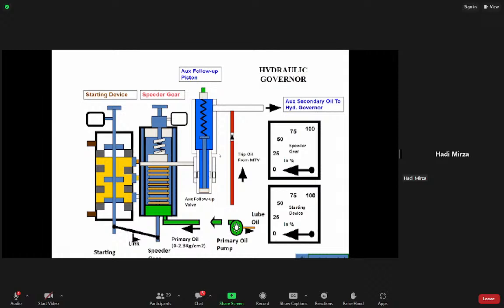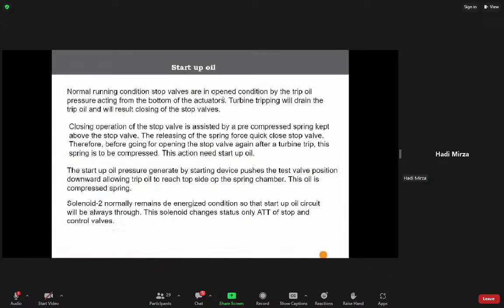Actually, this startup oil is required to reset the stop valves and hydraulic trip devices. In normal operation, stop valves are in opened condition and trip oil pressure acts from the bottom of the actuator. Turbine tripping will drain the trip oil and will result in closing of the stop valves. Closing operation of the stop valve is assisted by a pre-compressed spring kept above the stop valve.